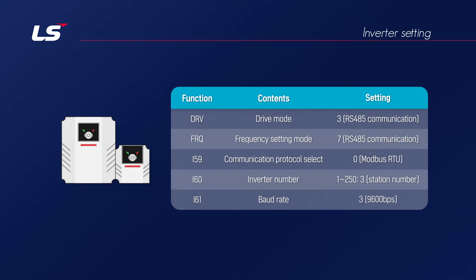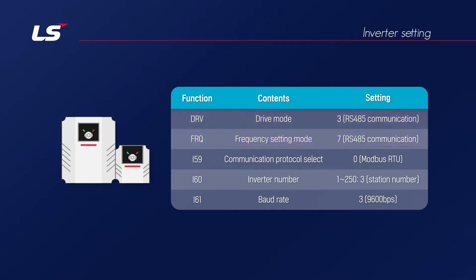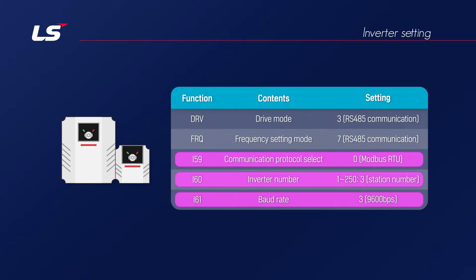The basic settings to control the reference frequency and run command of the drive are as follows: run command DRV 3, reference frequency FRQ 7. Also, you could change communication protocol I-59, station number I-60, baud rate I61, assigned to I-group I-59, I-60, I-61.